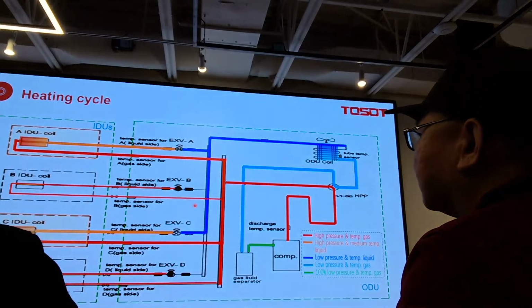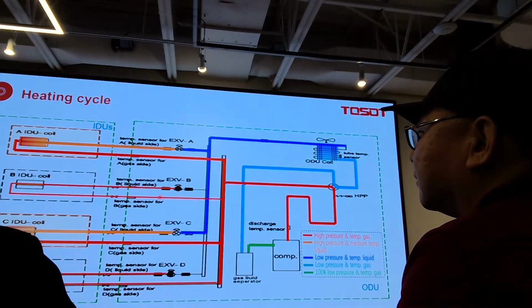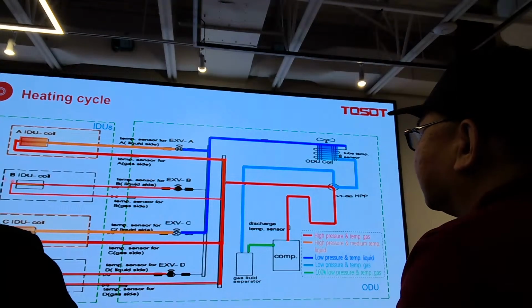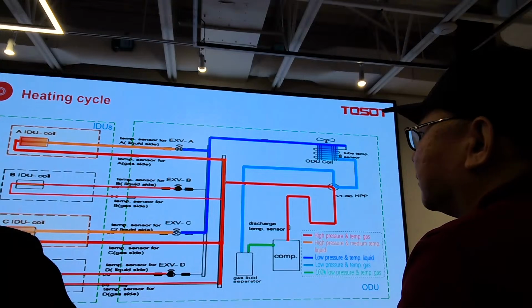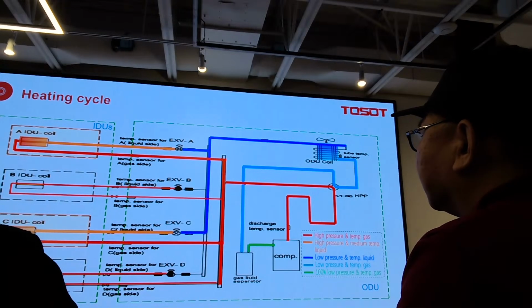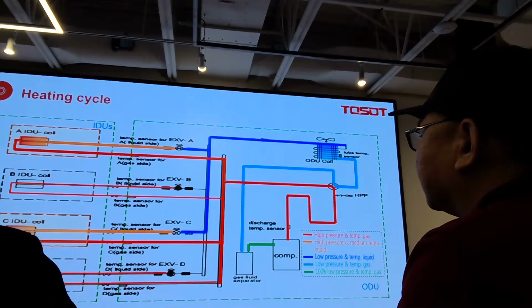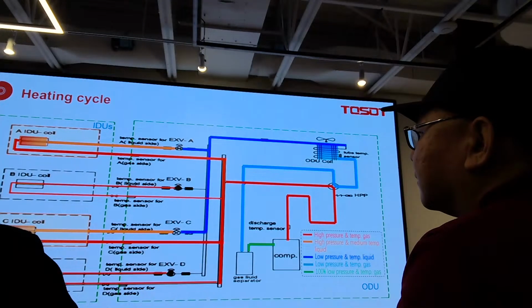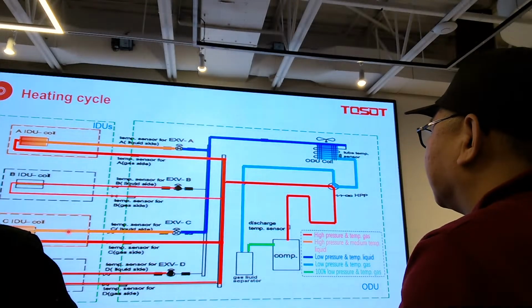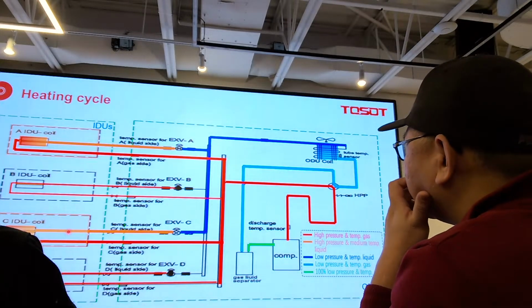That means more and more refrigerant will become liquid and accumulate at indoor unit B and D. And if too much refrigerant accumulates there, the circulating refrigerant for A and C will not be enough. In other words, A and C will be short of refrigerant.